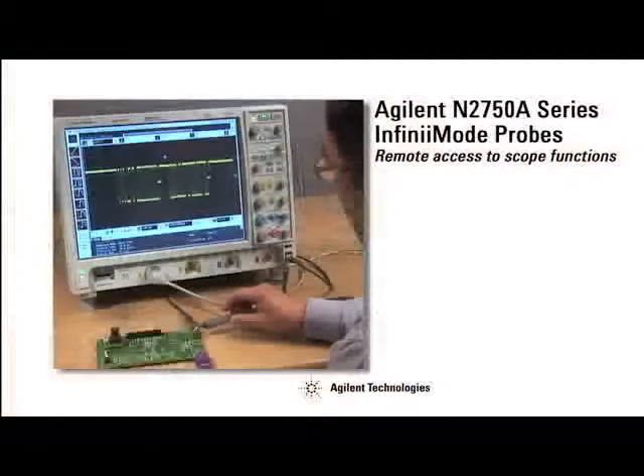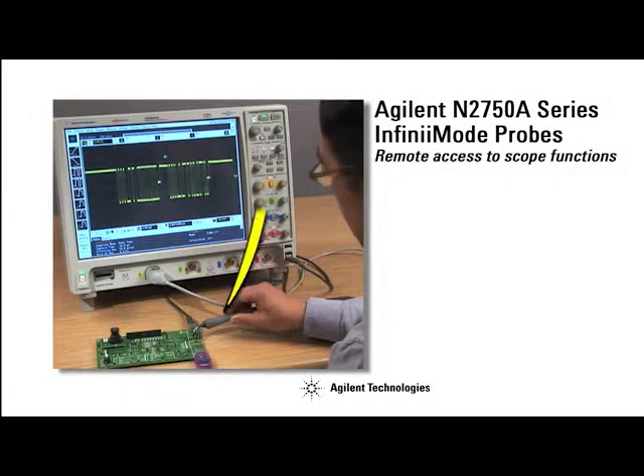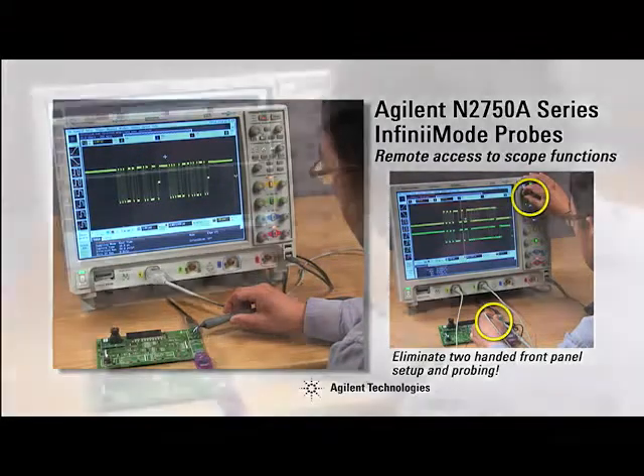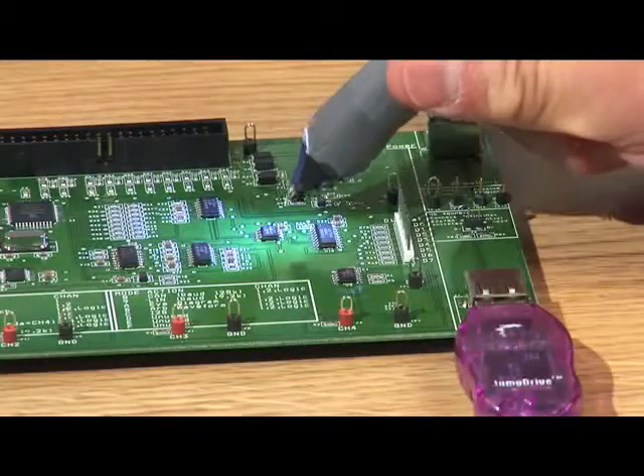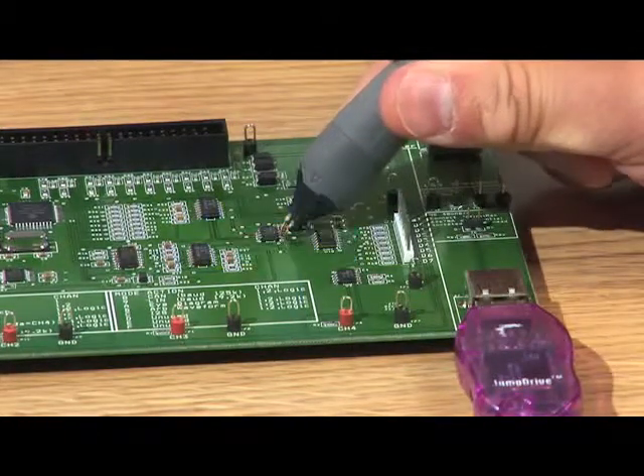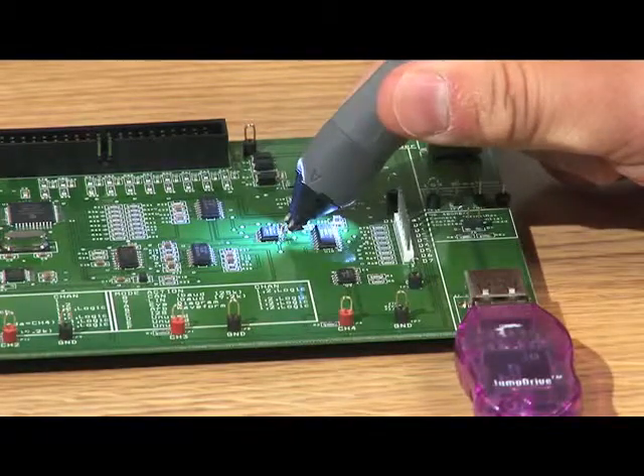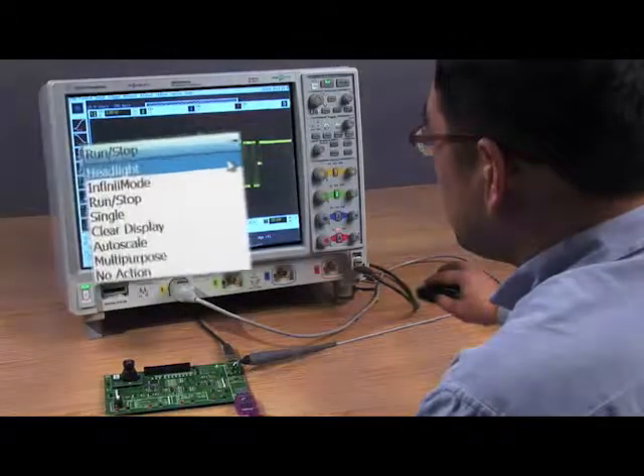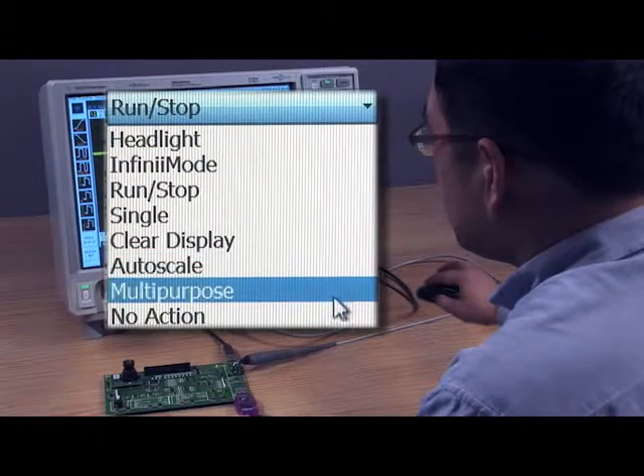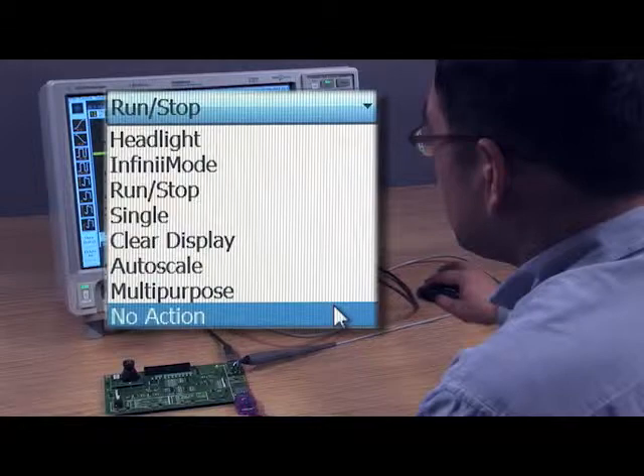Agilent's InfiniiMode probe also provides quick and efficient remote access to scope functions, eliminating your need to access the scope's front panel with one hand while holding a probe in the other. With the quick action scope control feature built into the probe, you can turn the built-in headlight of the probe on and off, or remotely control frequently used scope functions such as run-stop, autoscale, and many others with a simple press of the probe button.